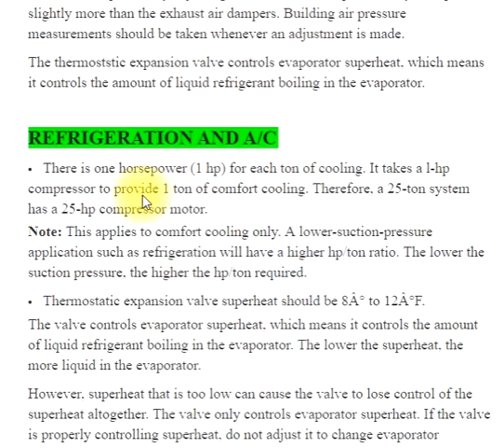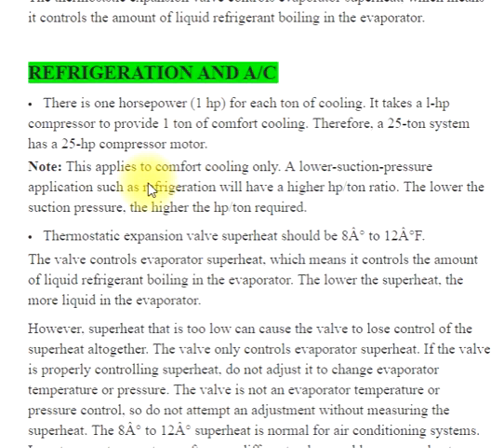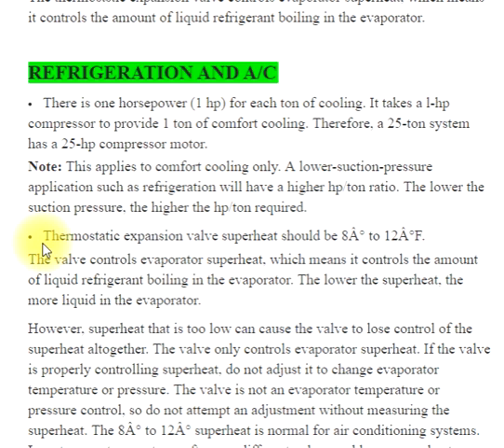Refrigeration and AC: there is 1 horsepower for each ton of cooling. It takes a 1 HP compressor to provide 1 ton of comfort cooling. Therefore, a 25-ton system has a 25 HP compressor or motor. Note, this applies to comfort cooling only. A lower suction pressure application such as refrigeration will have a higher HP-to-ton ratio — the lower the suction pressure, the higher the HP per ton required.